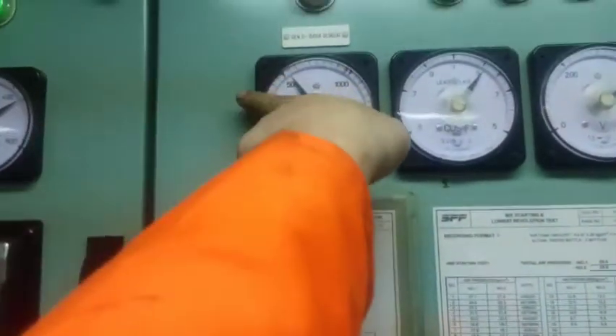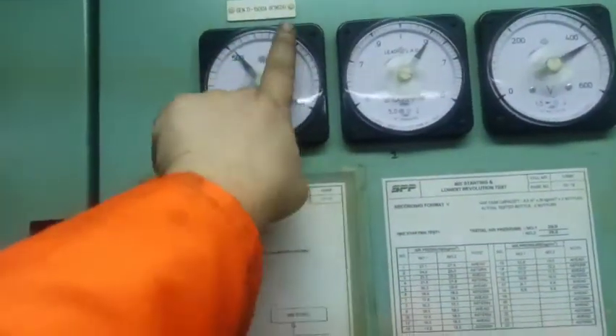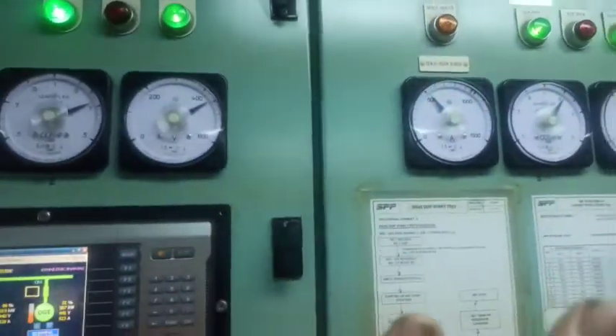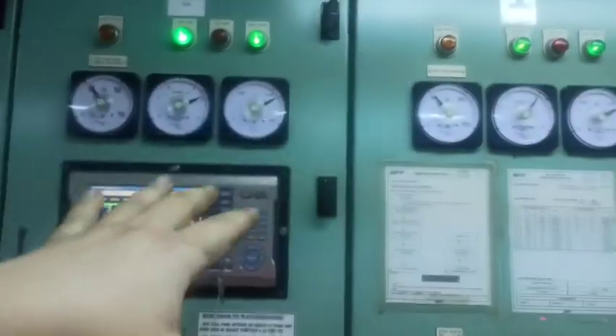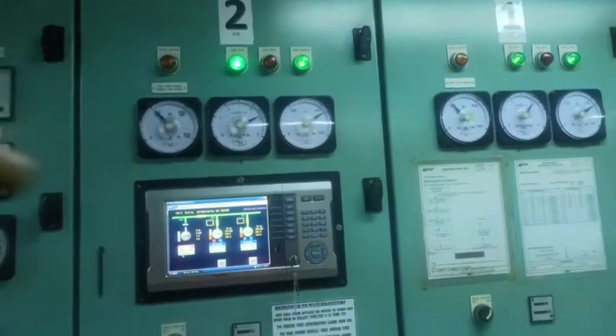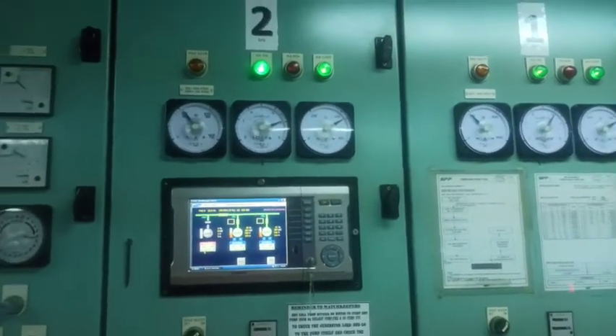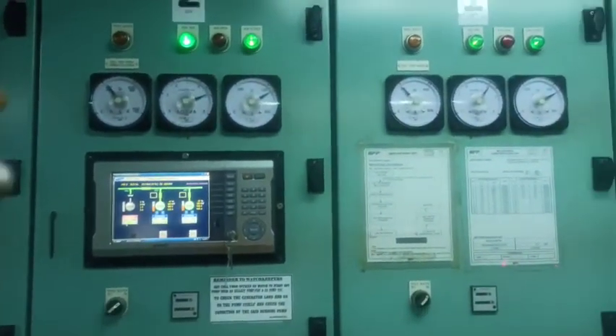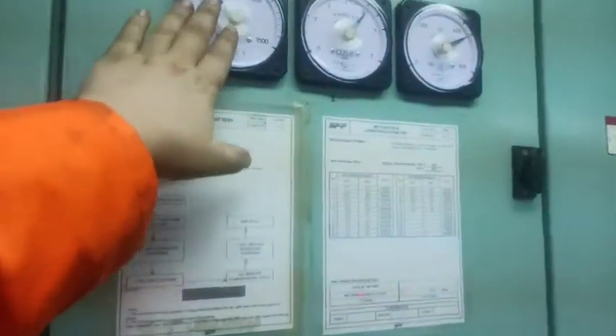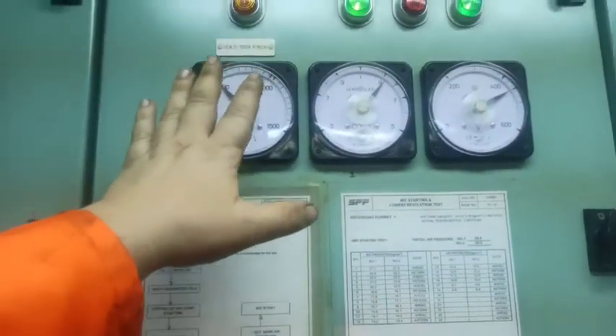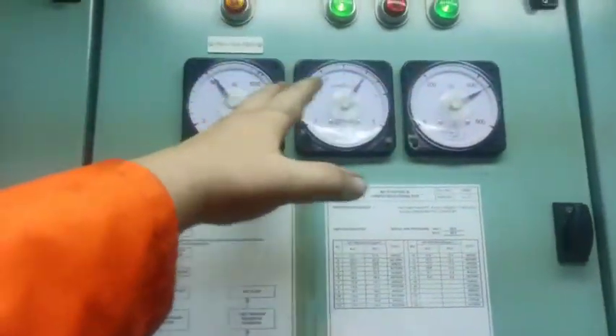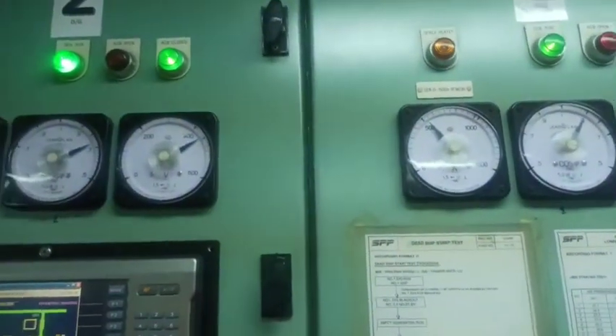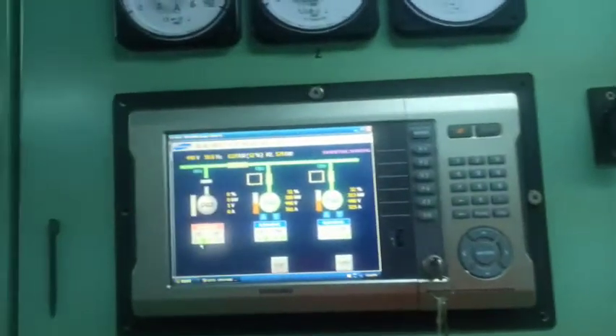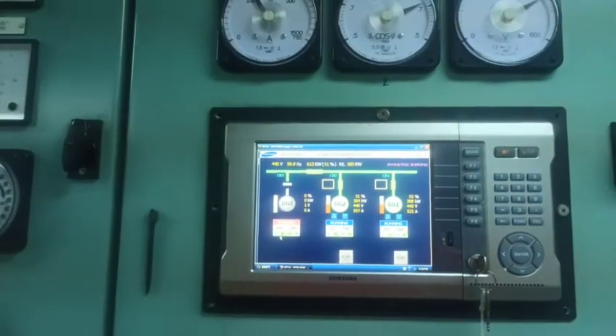If the AVR is not working correctly, you will see this here, with too much difference. But do not try this when the two diesel generators are working in parallel. When you like to do AVR adjustment, you must unload, you must have the generator running in idle, you do your adjustment, and after you connect and check if everything is okay or not.